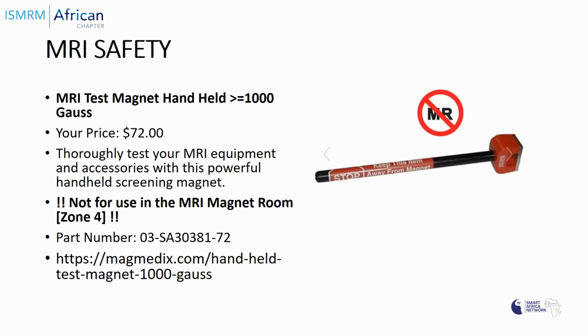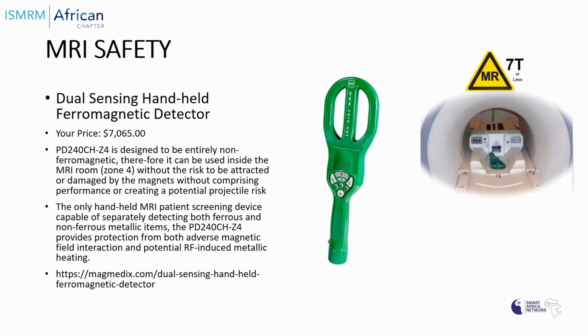This is an example of a handheld magnet detector. It's about 1000 Gauss, and I found this on the internet. It's also important to note that this cannot be used inside the magnet room, the room where the magnet itself is kept. This is another example of a handheld ferromagnetic detector. This one also I picked from the internet. This one can be used in the MR room, and it can even be used where the magnetic strength is even 7 Tesla. It's quite expensive though.